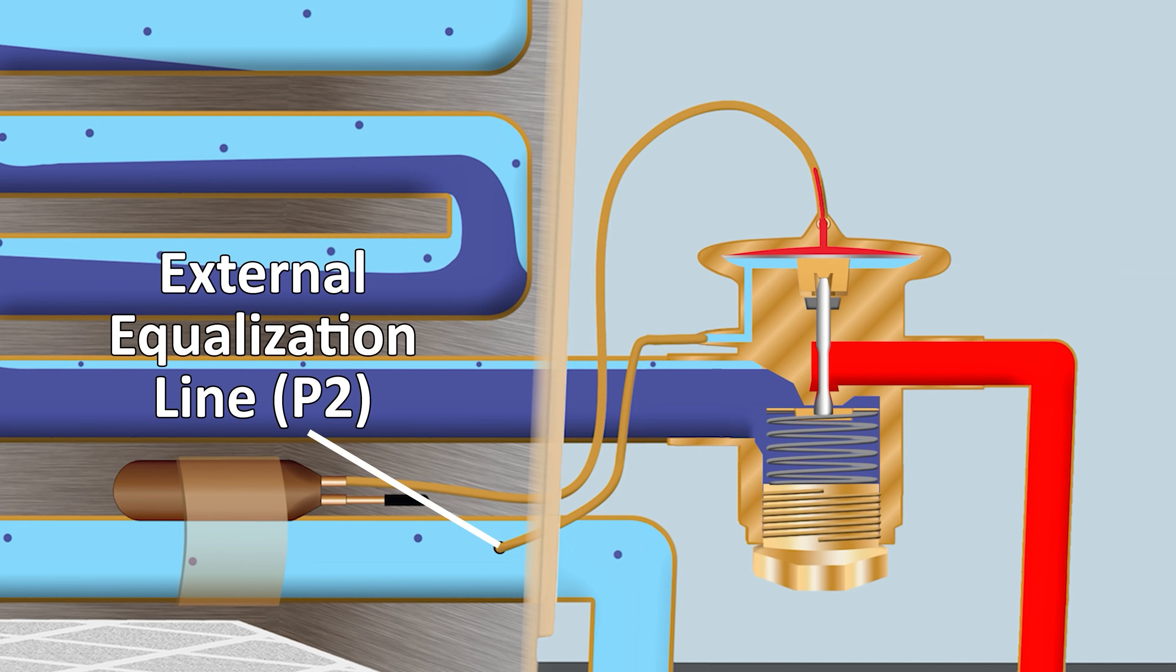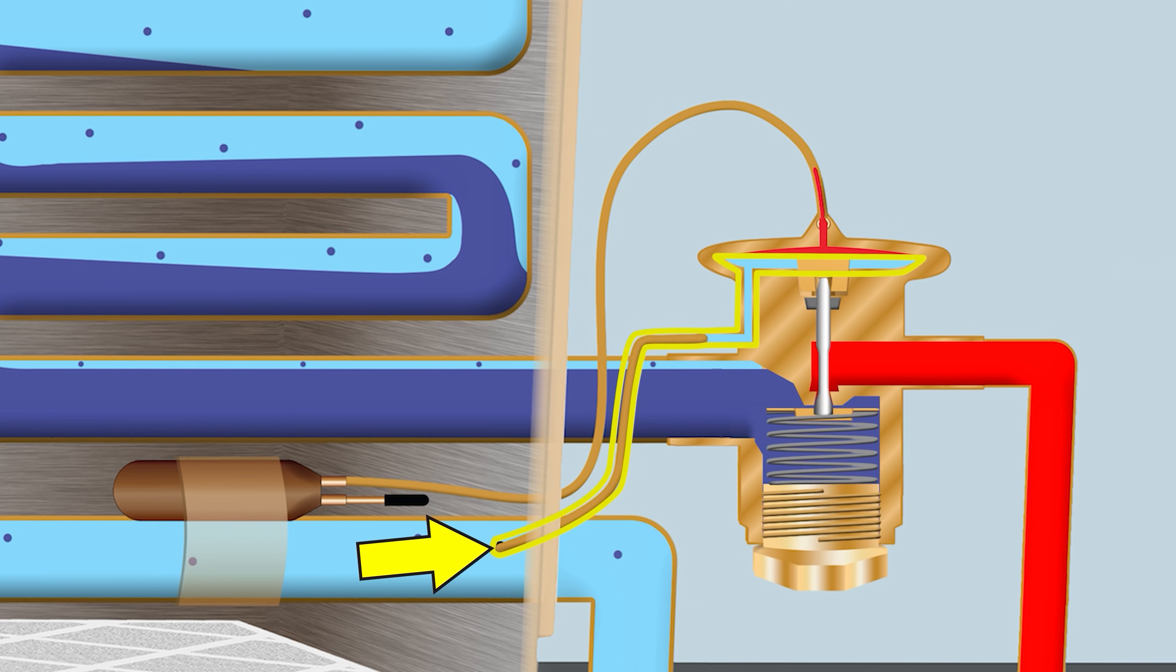Now P2, that is a closing force, and that is the external equalization line, such as this one right here where you have the line tapped into the vapor tube downstream of this bulb. You can also have an internal equalization line, and that would just get connected right over here to the outlet of the TXV.